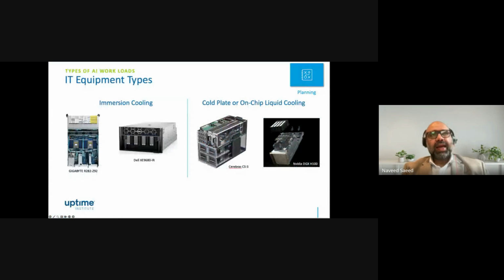The IT landscape is changing very quickly. The manufacturers are coming up with a number of servers that can support both direct-to-chip cooling as well as immersion cooling. If we look at immersion cooling, on the left side we have immersion cooling servers, so Gigabyte and Dell have immersion cooling servers, and on the right side we have cold plate and on-chip liquid cooling, and Cerebras and NVIDIA DGX H100 are supporting direct-to-chip cooling. So it depends upon which kind of IT hardware you're going to use.